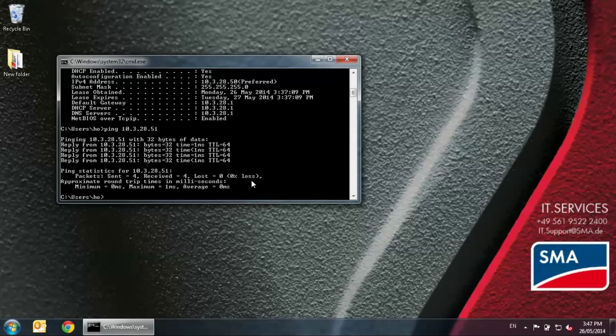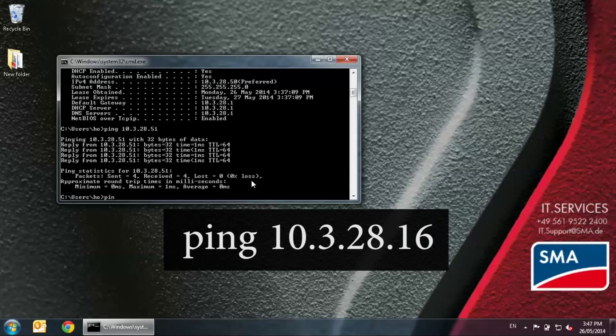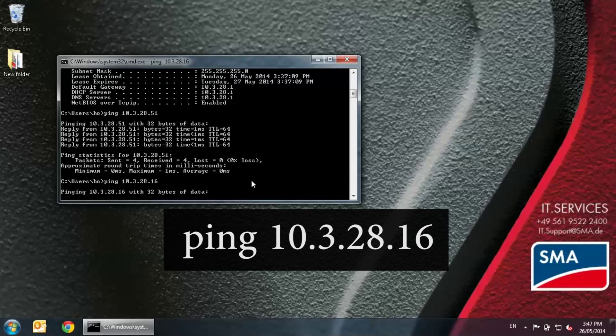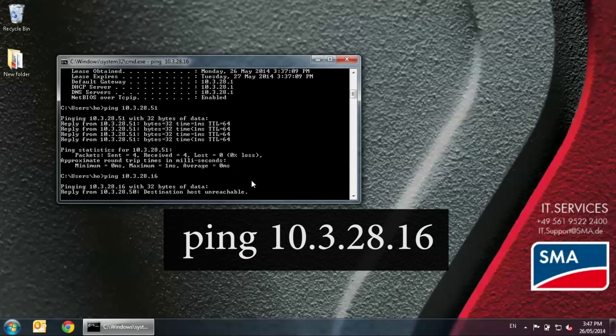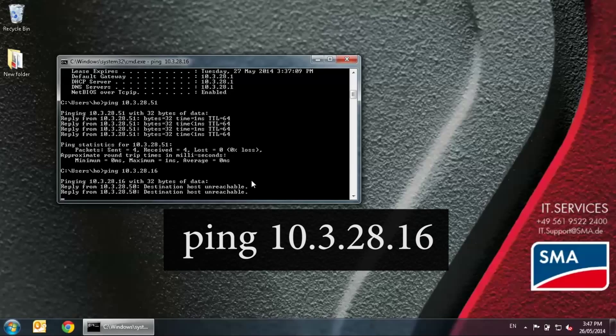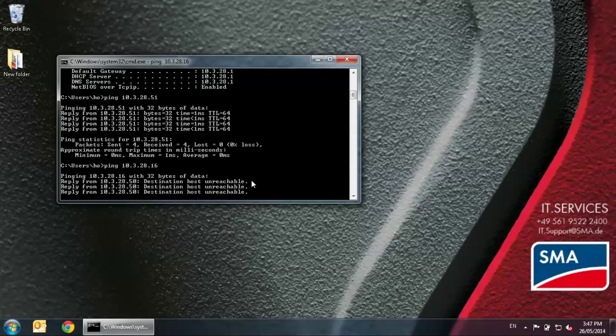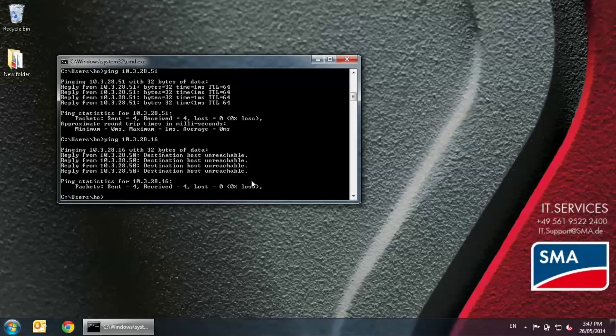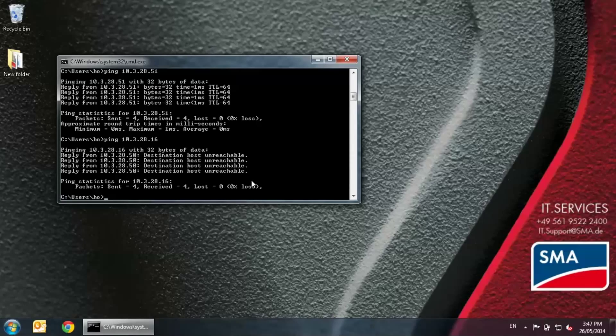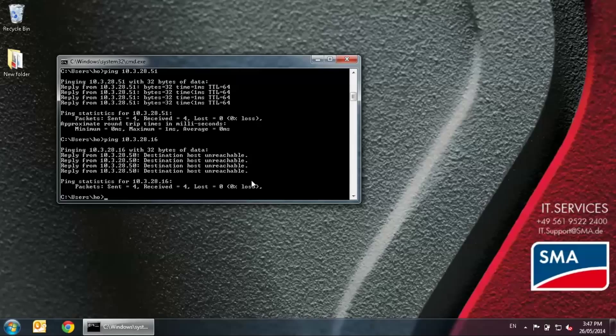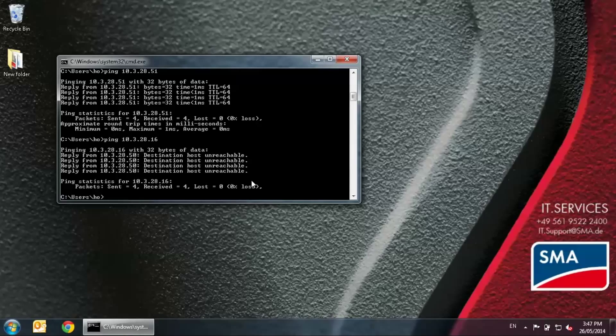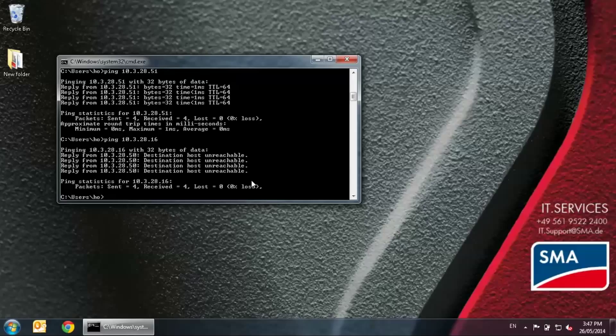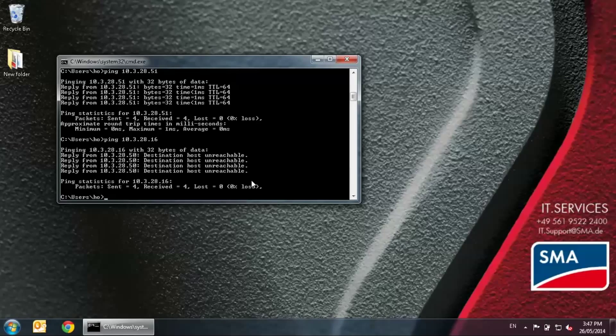So we'll do another ping. In the DOS screen, type in P-I-N-G, space bar, 10.3.28.16. You see here, destination host unreachable. This means that there is no device on the other end. So you can use the .16 address for the web box. Please consult with the IT staff as some IP address might be reserved for other purposes. So I strongly recommend to have an IT staff so they can provide you with all these details directly. Write this new IP address for the web box down to your sheet. And then we'll go to step two.